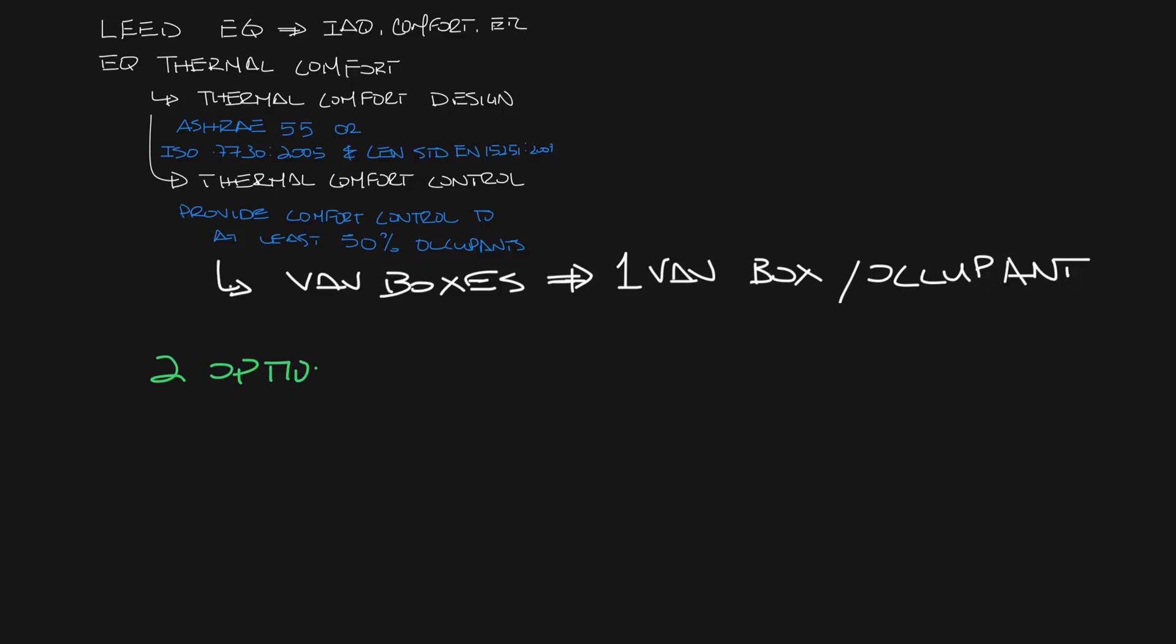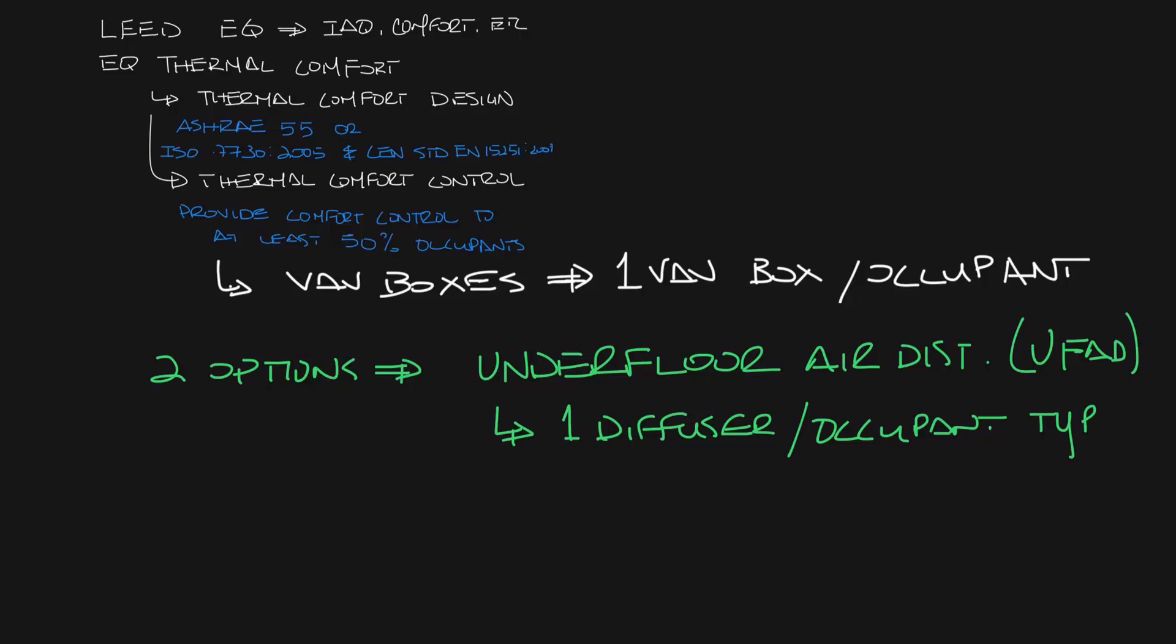But there are two other systems that can be used to achieve this credit. The most common system to achieve this credit is Underfloor Air Distribution. A typical UFAD system has one diffuser per occupant, and the diffusers can be user-adjustable.